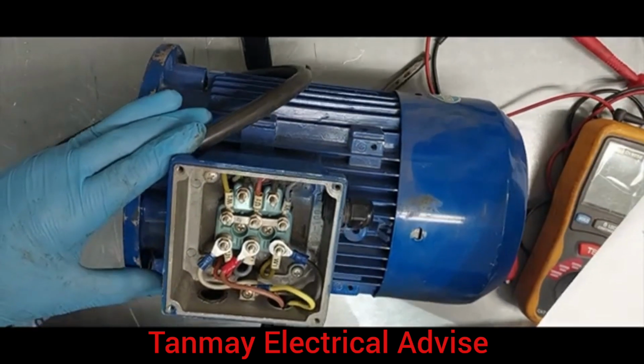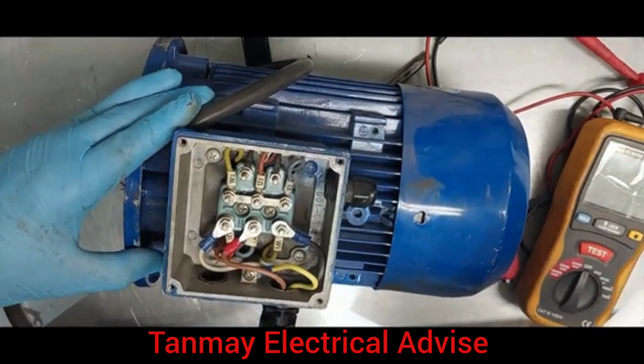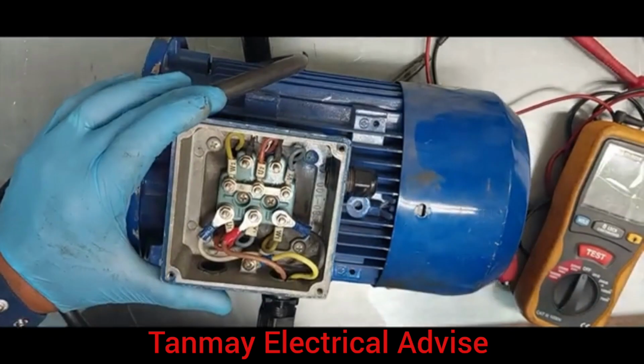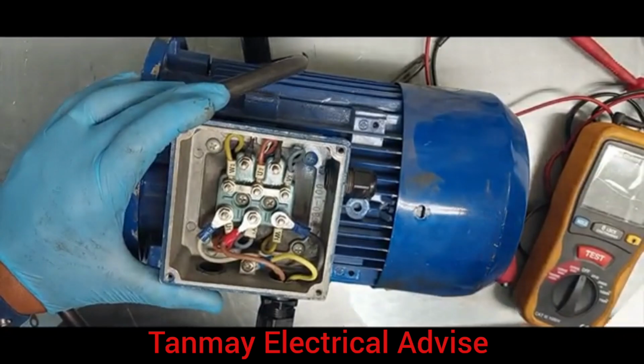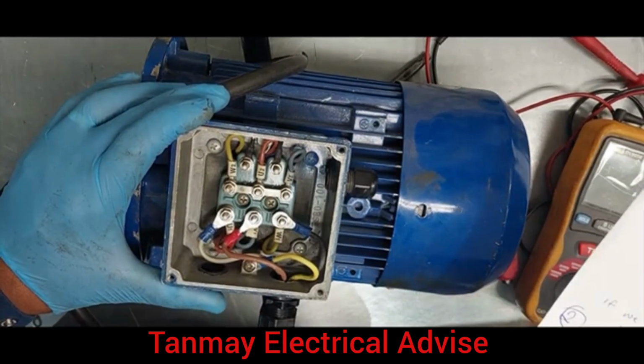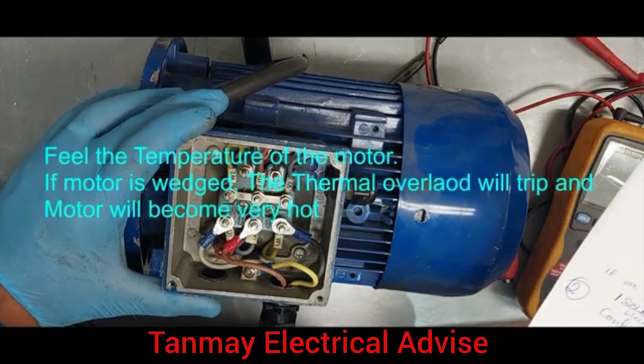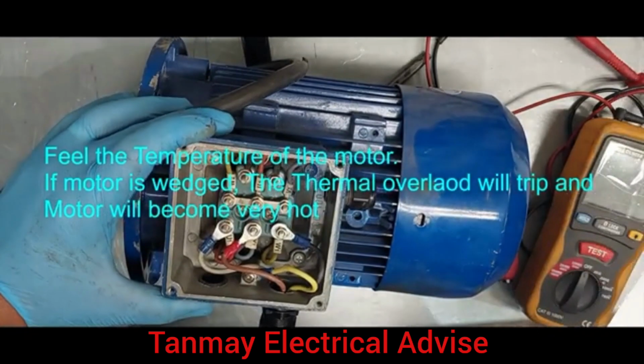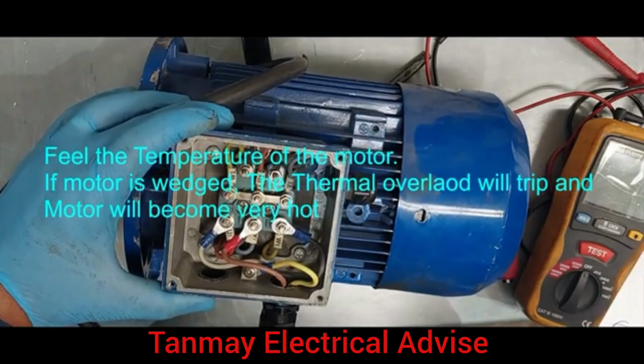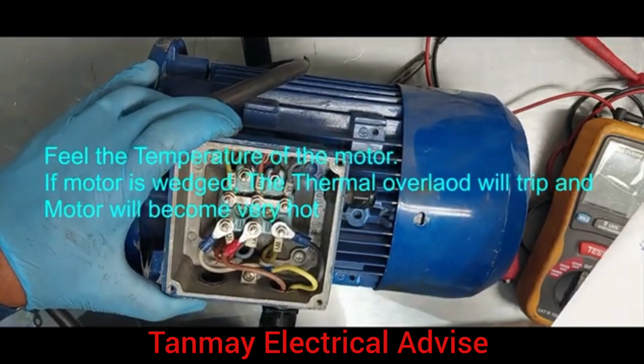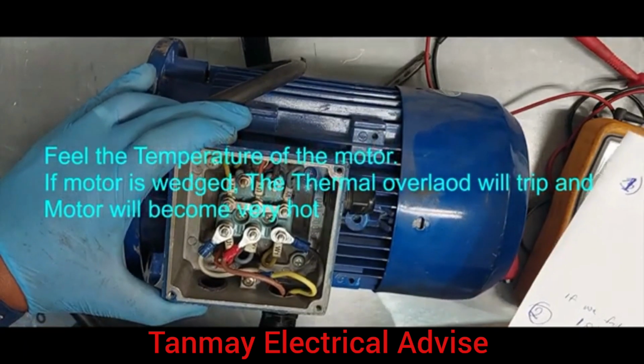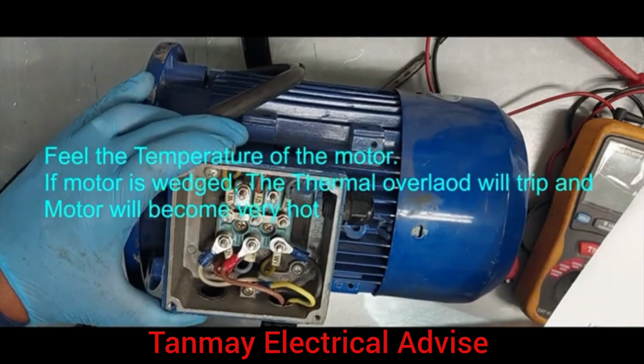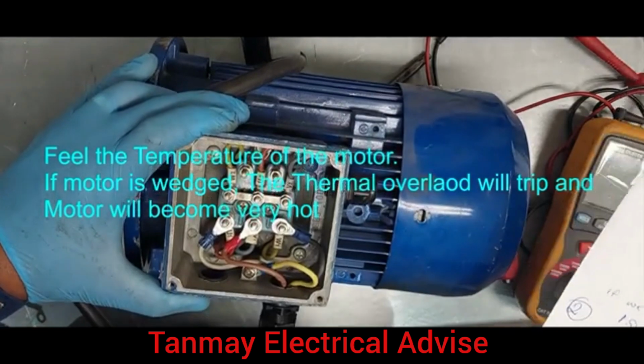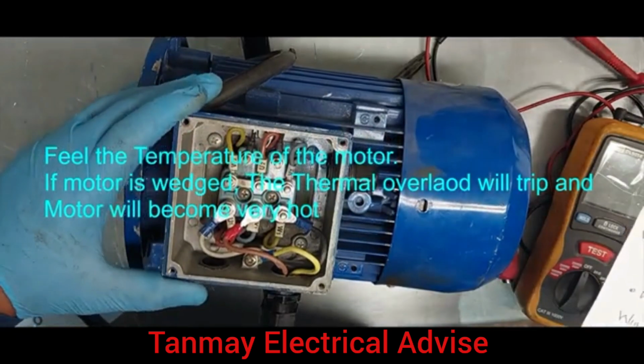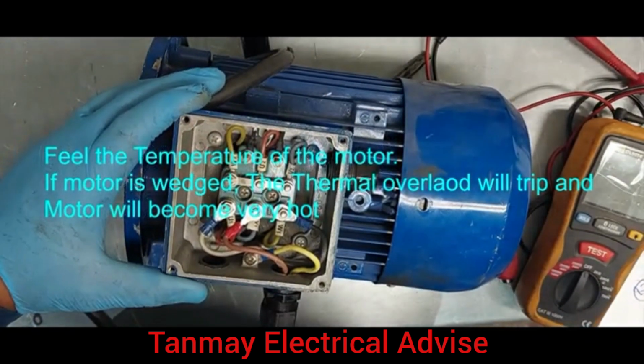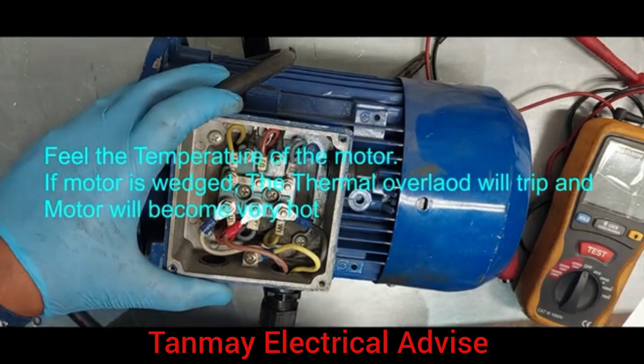the next thing to check is to see if it's mechanically held up. Assuming this motor is running a conveyor belt, we have to check to see that nothing is trapped in the rollers of the conveyor. We have to check to see that nothing is wedged in the gearbox, so that the moving conveyor is free of any obstacle that might be wedging it and keeping it from being mechanically trapped. And then we also have to examine the bearing to make sure that the bearing is still all right. But normally the bearing takes time before it seizes up. It gives you signs that it's going bad, so it takes a very long time for the bearing to go bad and get the motor stopped mechanically.